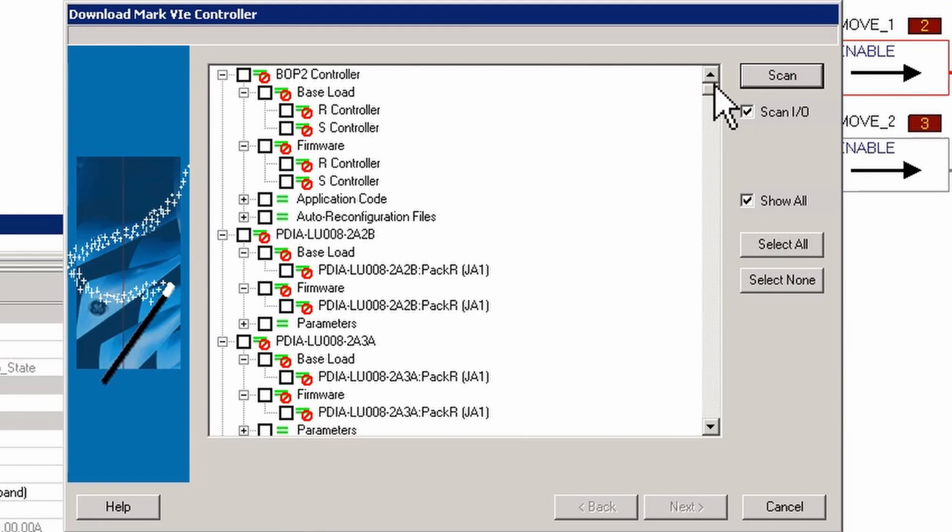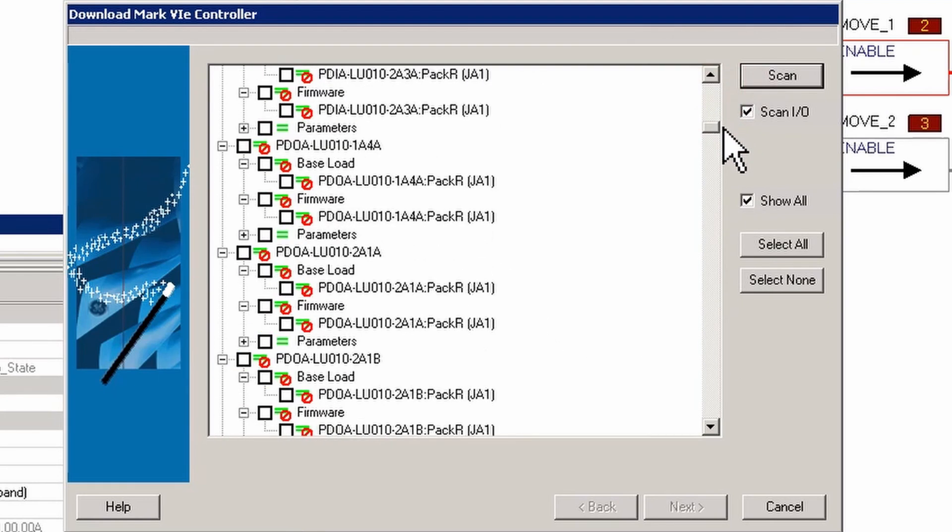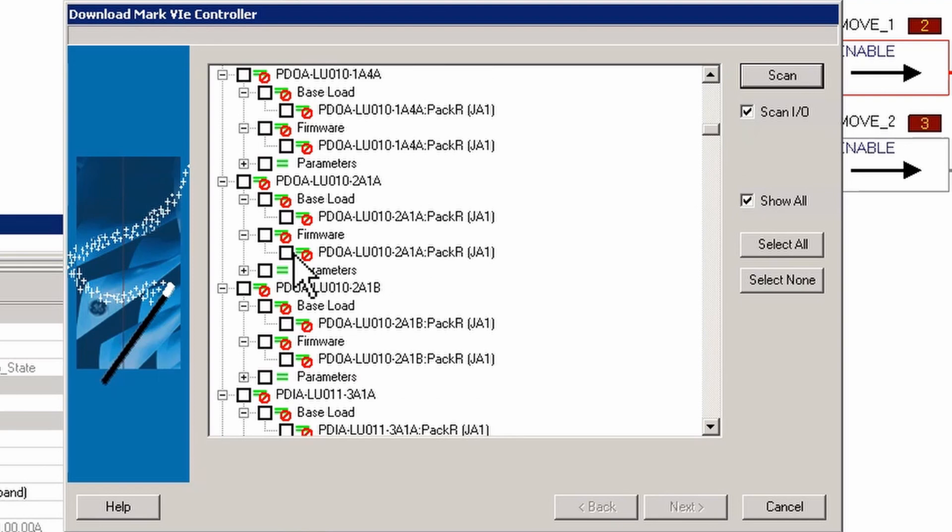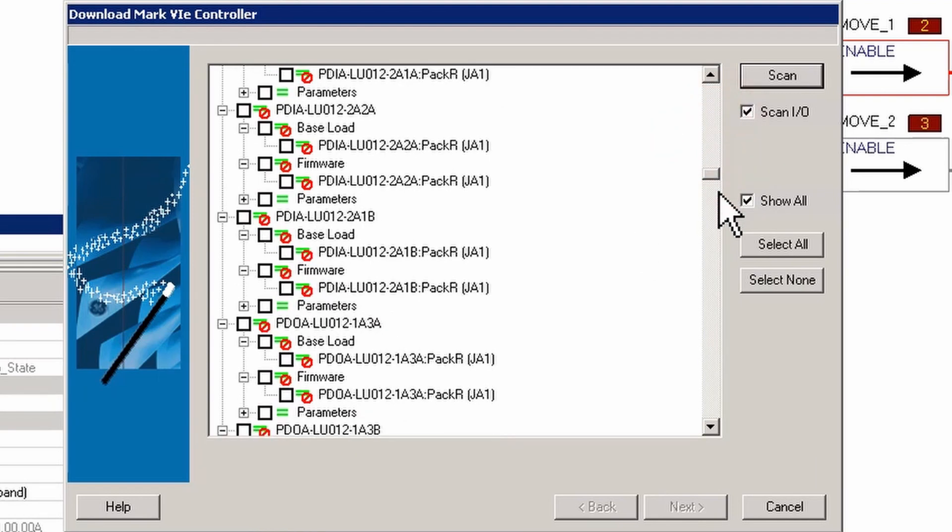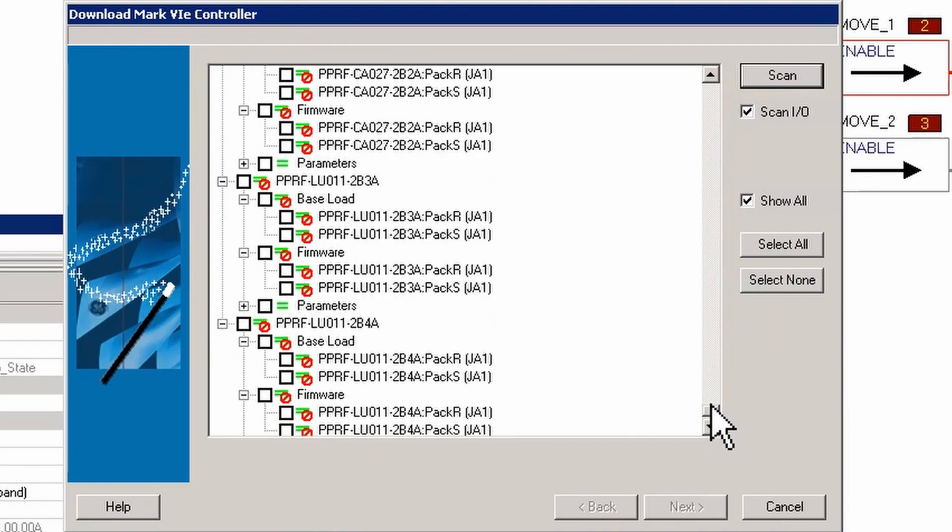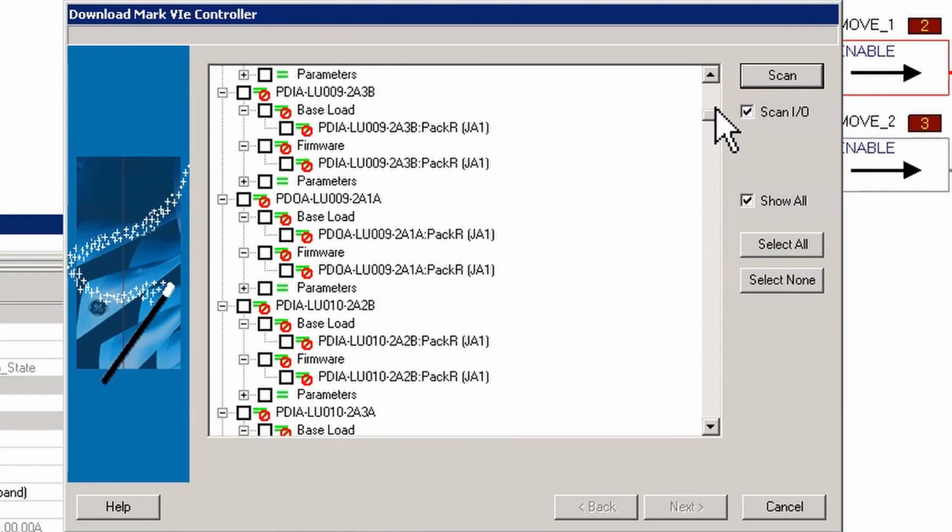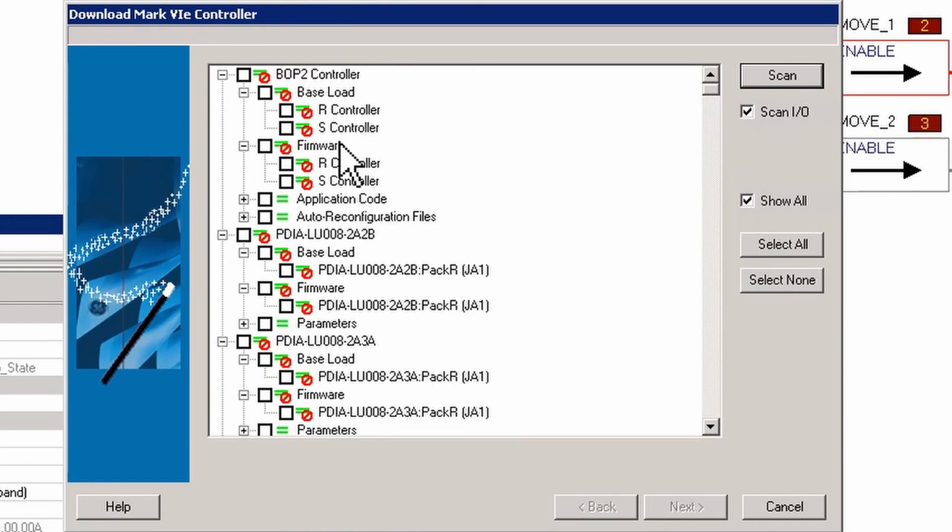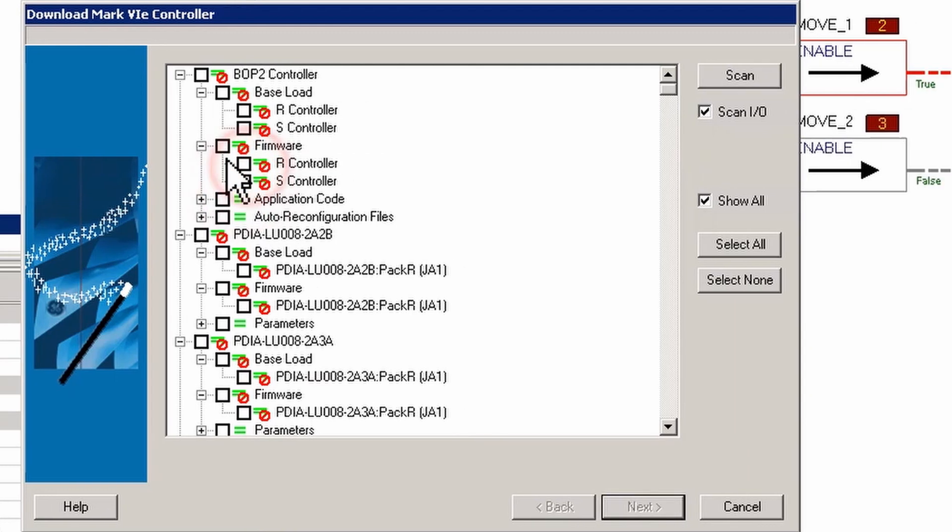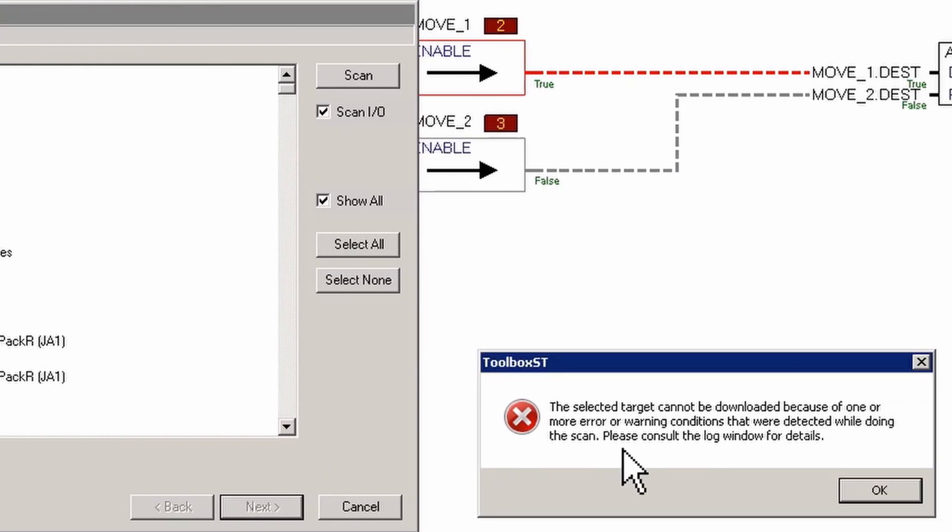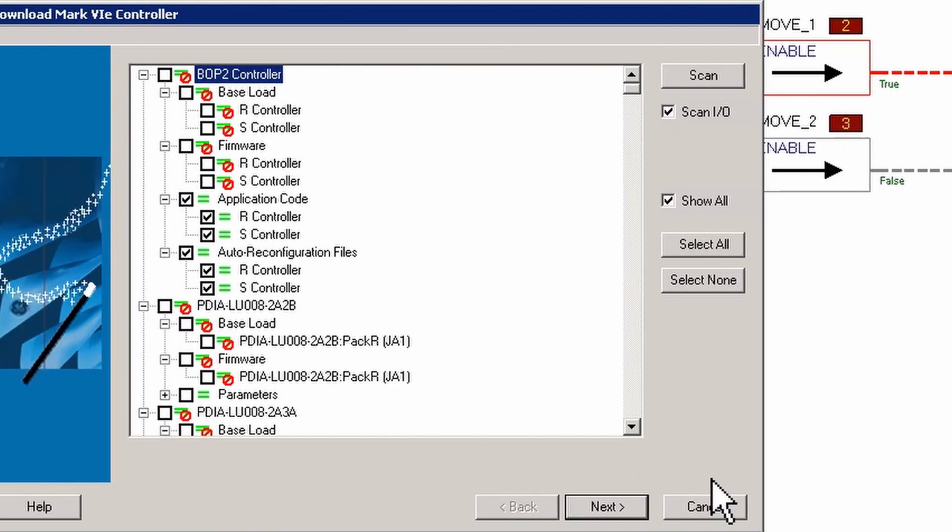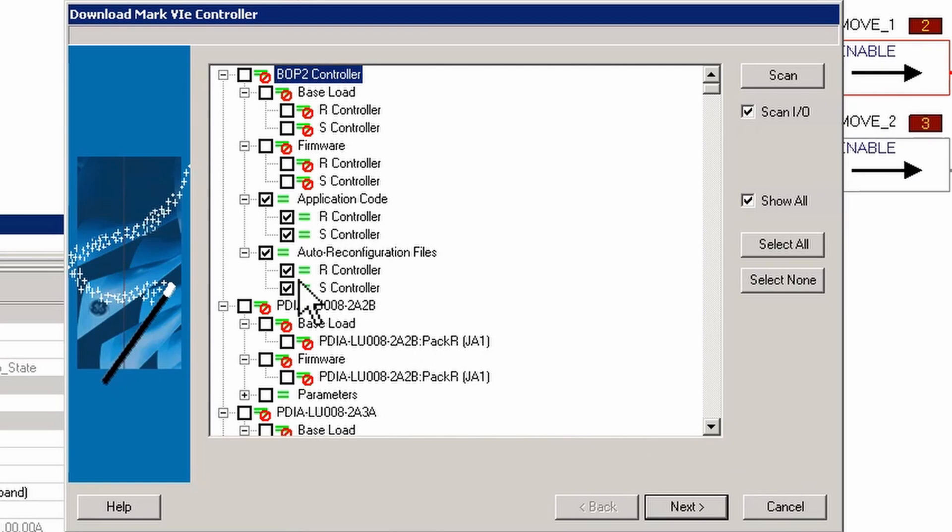You'll see these little anti or no marks for anything that you want to do here that would require the processor and/or an IO pack to reboot. It'll no longer allow it. You can still download parameters, but anything that's going to require the pack to reboot or the processor to reboot, it will not let you select.